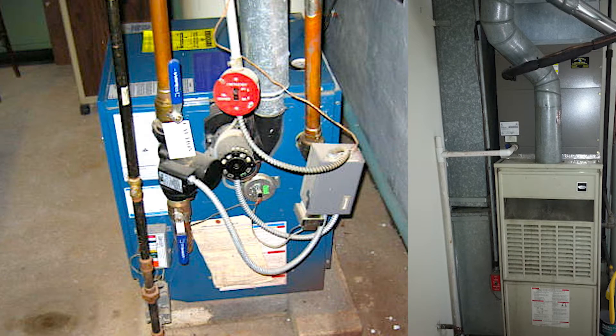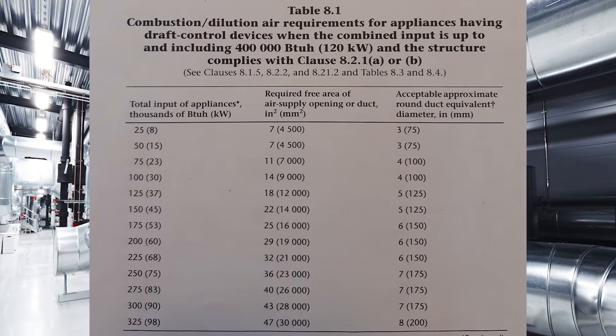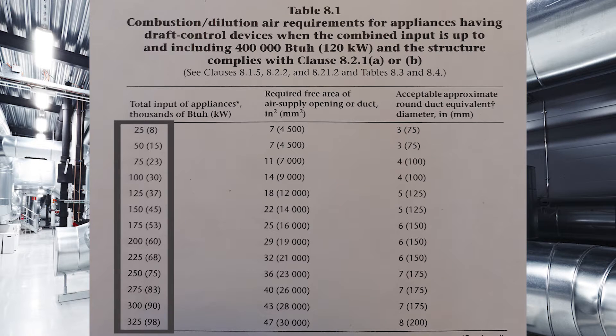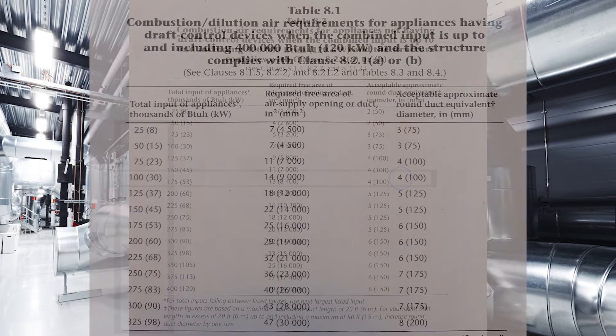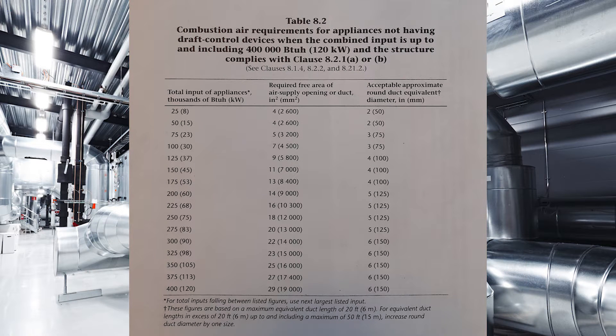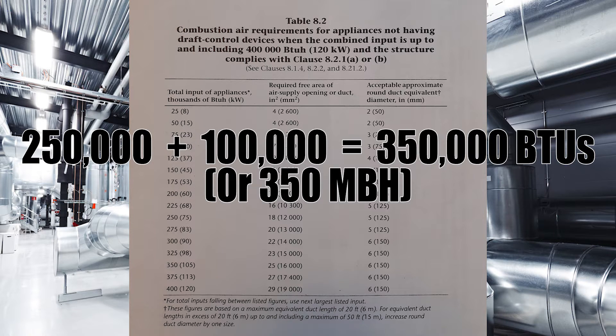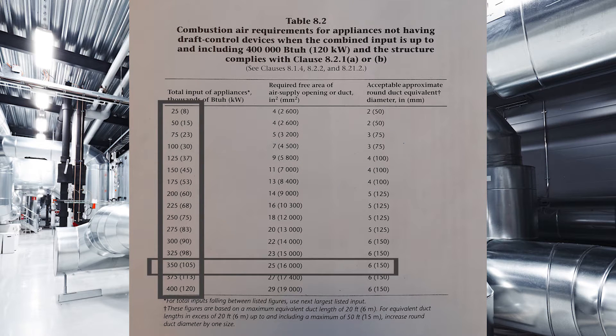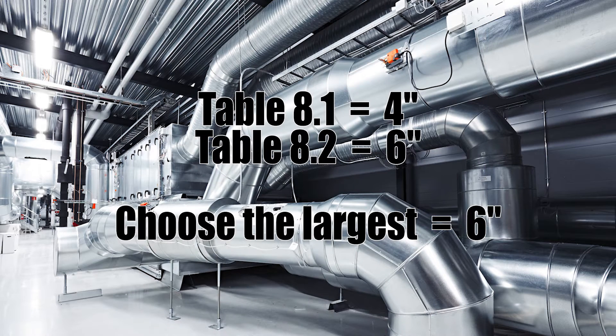For a last example, let's flip the tables. Now I have a 100,000 BTU furnace equipped with a drafthood and a 250,000 BTU fan-assisted boiler. For table 8-1, I only use the drafthood equipped appliance — that's 100,000 BTUs. I come down to that, go across to the right, and I need a 4-inch air supply. Now I check all appliances combined with table 8-2: 100,000 plus 250,000 is 350,000 BTUs. Going down to 350 in table 8-2 and across to the right, I require a 6-inch round air supply. That's bigger than the 4-inch from table 8-1, so 6 inches will be my size.